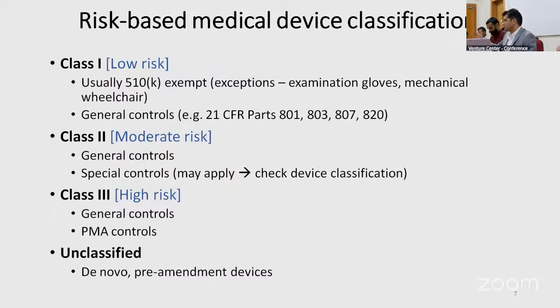So the thing to remember here is the CFR is binding. Then there's the next level, which is FDA guidance documents. Those are essentially FDA's recommendations. Those are also kind of the special controls. They'll be defined as special controls. Those are what FDA is recommending, that's what you follow. We generally expect that's what you're going to follow. And if you don't, you've got to explain why not. But those are the recommendations.